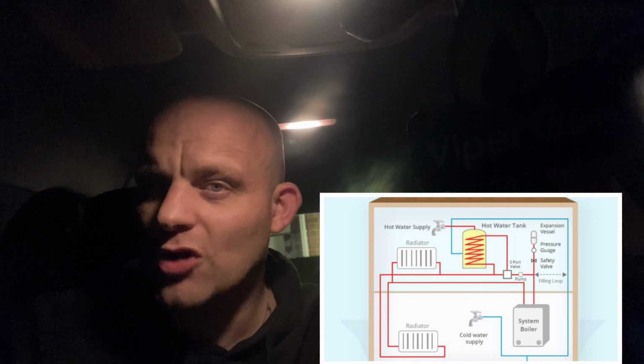And when it comes to designing a system, you have to think about the services, the demand. So this property in total is going to have about 3 showers. If you have a bar shower, they do 6 litres per minute. So a performance combi can handle that. Unvented cylinders, they're all good, but you've got to fit the cylinder, the system boiler, the controls, the motorised valves. There's 2 items to service. It's a space issue as well. So enjoy the video. High performance storage combis.